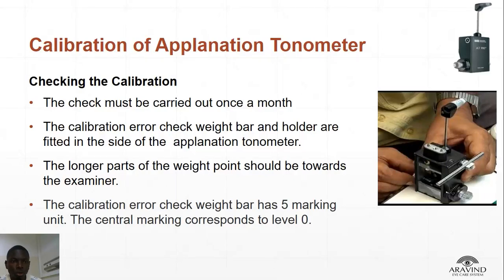Calibration of Applanation tonometer. Checking the calibration. The check must be carried out once a month. This is very important. The calibration error check weight bar and holder are fitted on the side of the Applanation tonometer. As you sit in front of your screen, on your right, the longer part of the weight bar should be towards the examiner. This is it. This is the longer part towards the examiner. The calibration error check weight bar has 5 marking units. The central marking corresponds to 0.